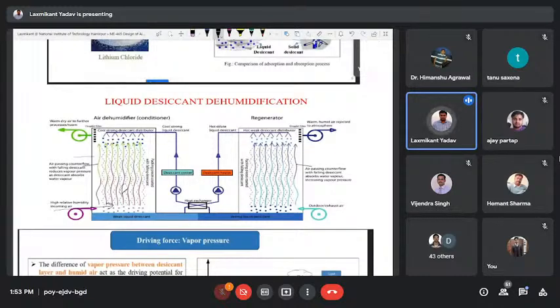In some arrangements a heat exchanger is provided here to compensate for this heat of absorption. In this figure the heat exchanger is not shown, but generally we provide a heat exchanger in the fill to neutralize this heat of absorption. Here the air will be warm dry air, which is further used either for drying or for air conditioning. Now the desiccant becomes a weak liquid desiccant, saturated with water vapor. Because it is saturated, it cannot absorb further moisture, so it requires regeneration.